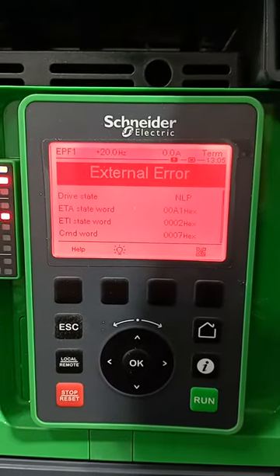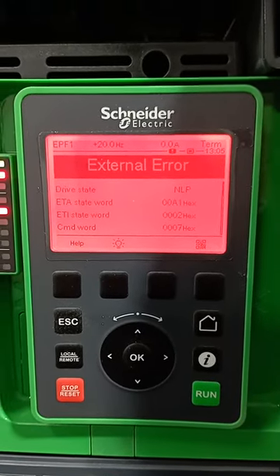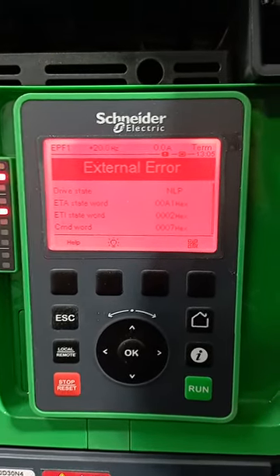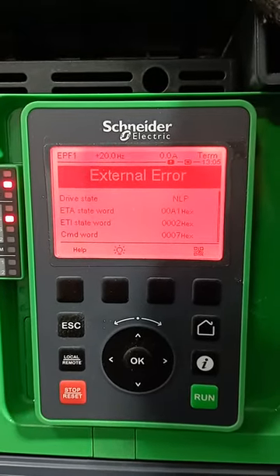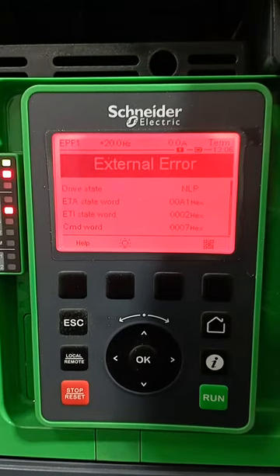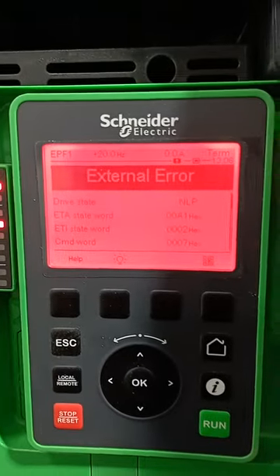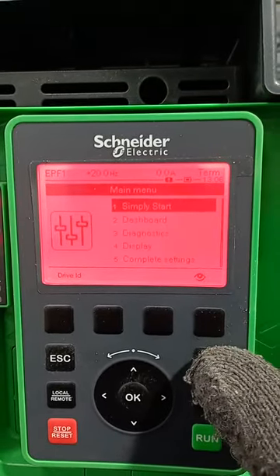On today's video I want to show how to clear an external error fault, that is EPF1 fault, in Altivar Process ATV930 Schneider Electric. An external fault — sometimes if you buy a new VFD and power it on, you see this error. This simply means that there is a logical input that is supposed to be active but it's not active. So basically, to clear this external error fault, you have to deactivate that logical input.